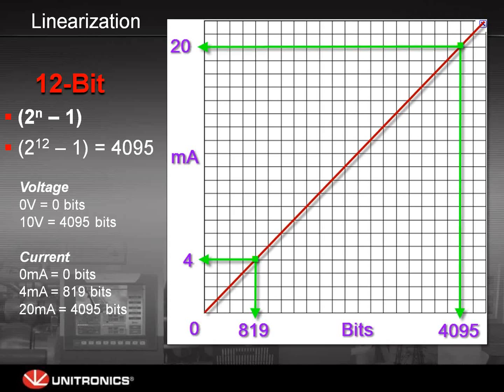The same is true for current. Zero is always equal to zero. Even if you're using a 4 to 20 milliamp sensor, your zero milliamps will be zero bits, your 4 milliamps will be 819 bits, and your 20 milliamp will be 4,095.